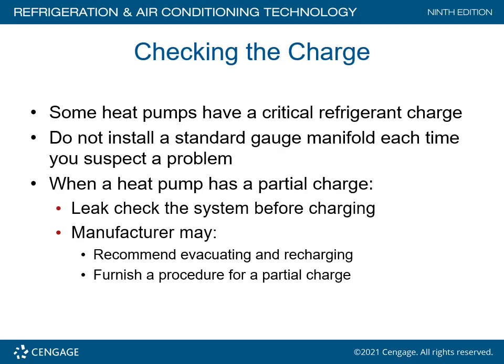Check the charge. Now this can be difficult. Some heat pumps have a critical refrigerant charge. I mentioned that. Do not install a standard gauge manifold each time you suspect a problem. When a heat pump has a partial charge, leak check the system before charging. The manufacturer may recommend evacuating and recharging. Furnish a procedure for a partial charge. There's no one-size-fits-all service for fixing a system that is not charged properly.